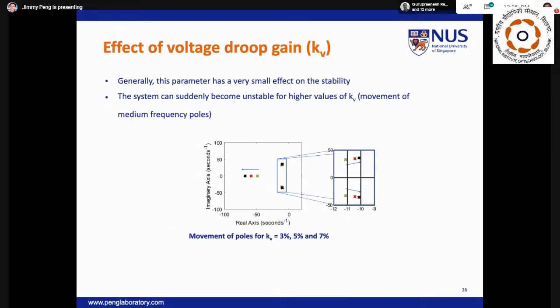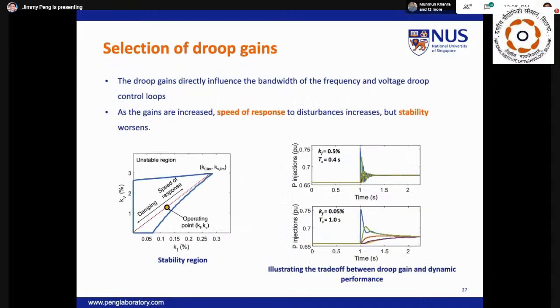Now, the voltage Droop pole plays a relatively minor role in comparison. As the gain increases, the real pole shifts to the left-hand side of the plane, but this also triggers the frequency Droop to slightly shift to the right-hand side of the plane. Now, to summarize, the selection of Droop gains will affect the control bandwidth as witnessed in these eigenplots in earlier slides. The purpose of selecting high Droop gains is to increase the speed of response to disturbances. However, this has a degrading impact on the network stability.